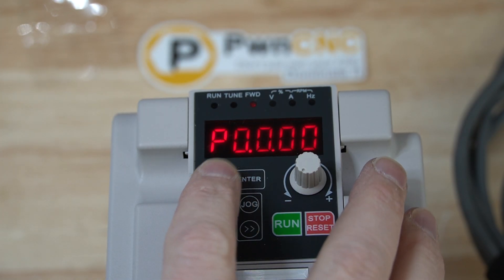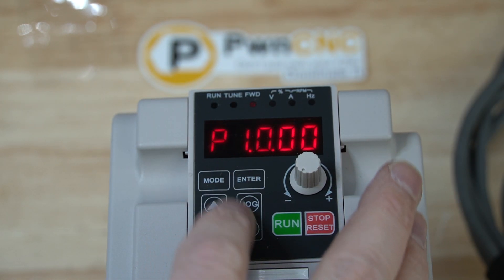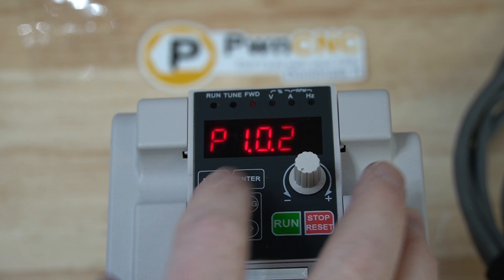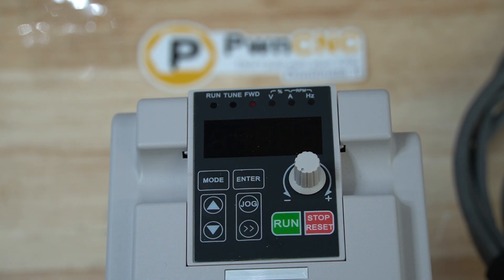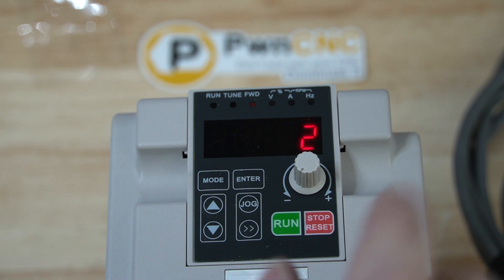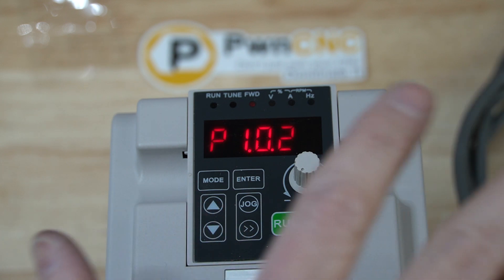All you do is hit mode. This brings you into the programming codes. Switch it over to 1, 0, 2 — so P1.02. Hit enter. We're going to change that from 0 to a 2. Now the 2 basically means that whenever this thing is running here — let me hit mode to go back to normal operating mode.